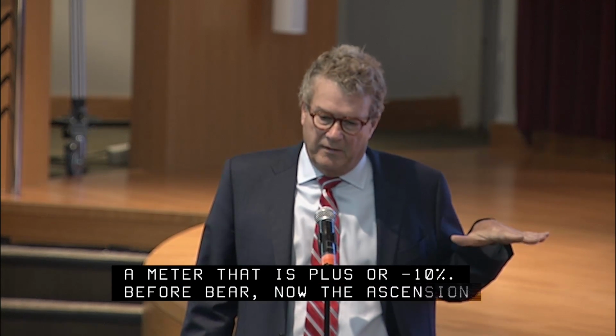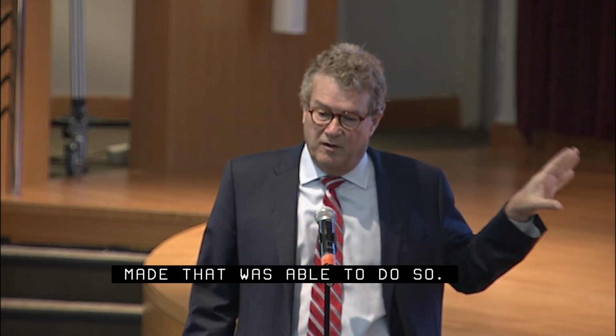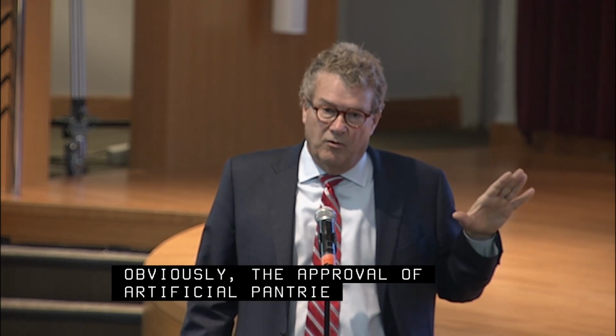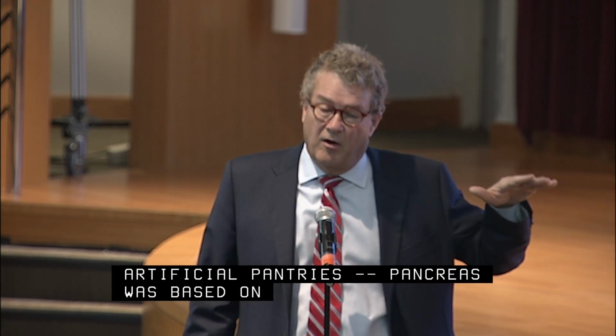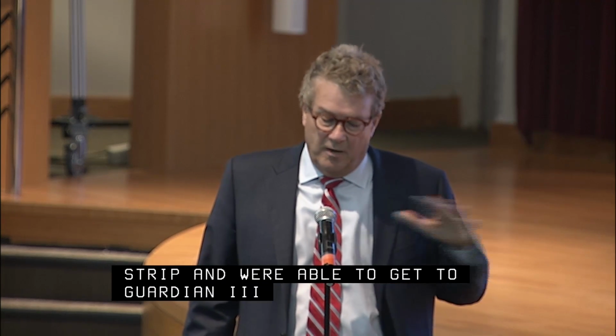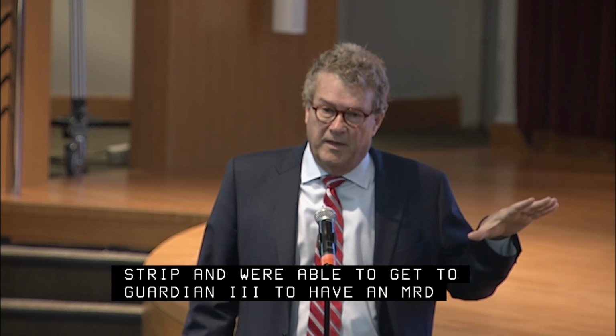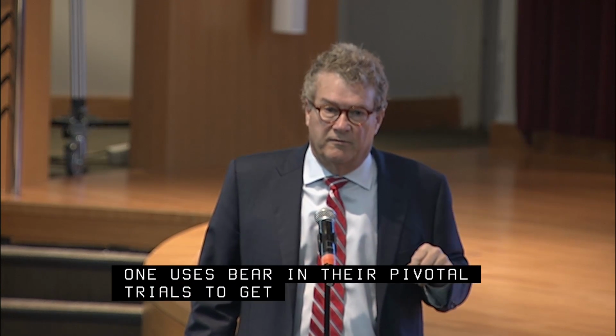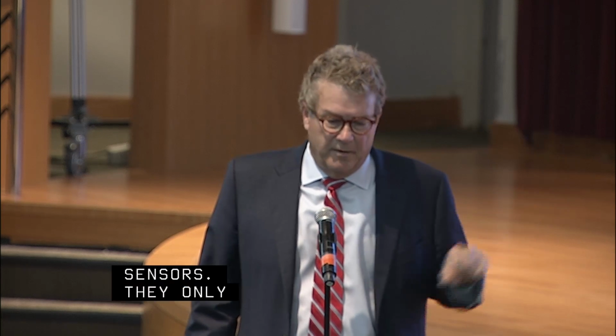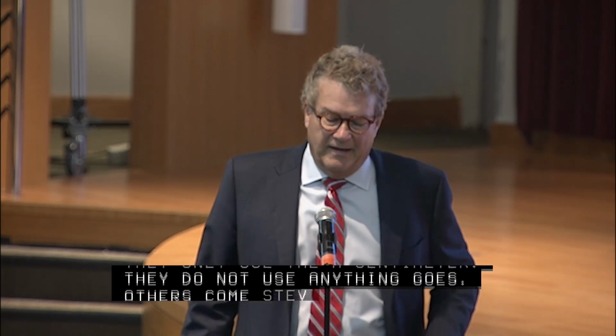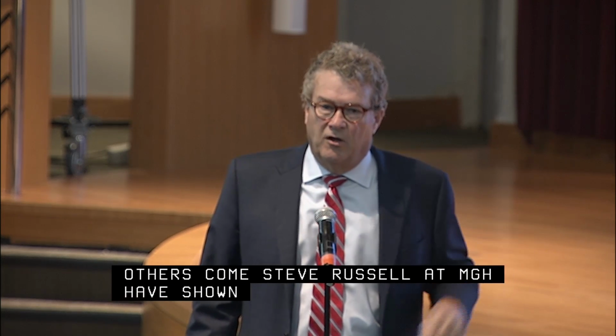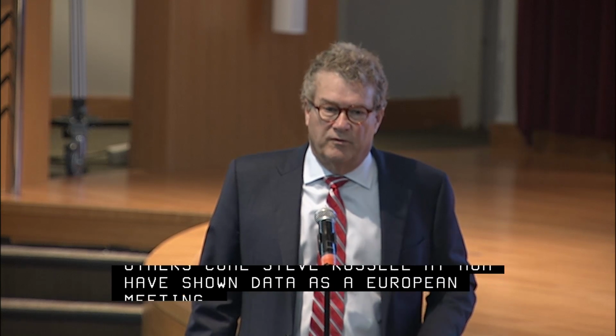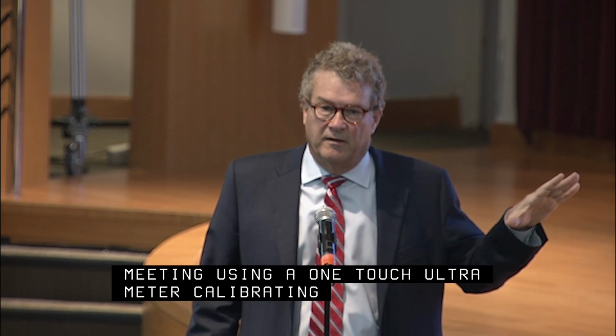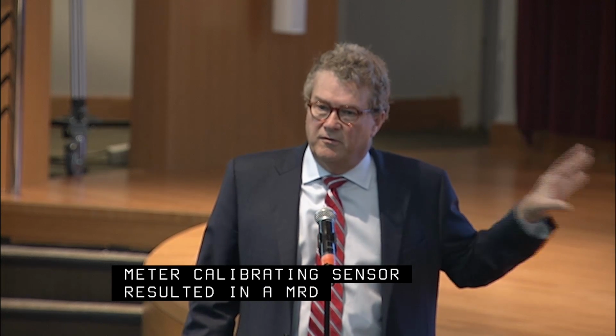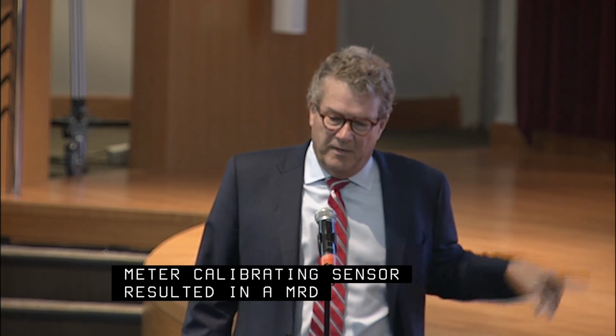So obviously the approval of Medtronic's artificial pancreas was based on the Contour Next, both meter and strip. They were able to get the Guardian 3 to have a MARD of 9.6%. Dexcom, which you'll hear later, uses Bayer in their pivotal trials to get approval of their sensors. They only use the Essentia meter. They don't use anything else. Others have, Steve Russell up at MGH had shown data at a European meeting using a OneTouch Ultra meter calibrating a Dexcom sensor resulted in a MARD of 18%, meaning the sensor is not accurate enough to be part of the artificial pancreas.